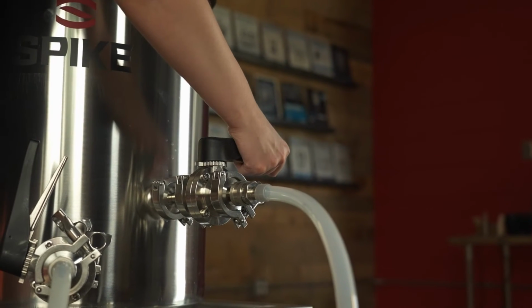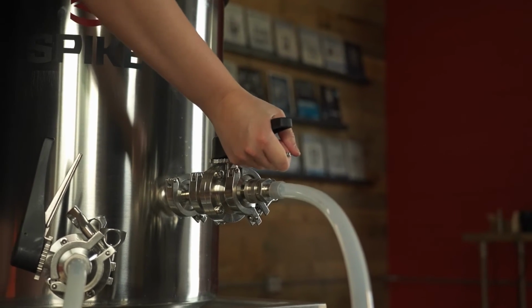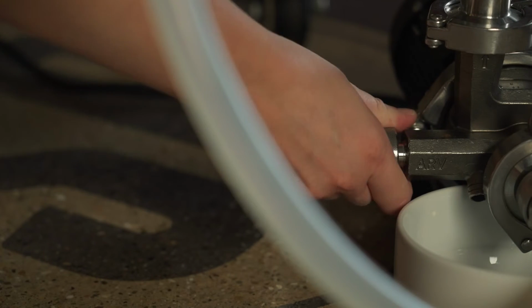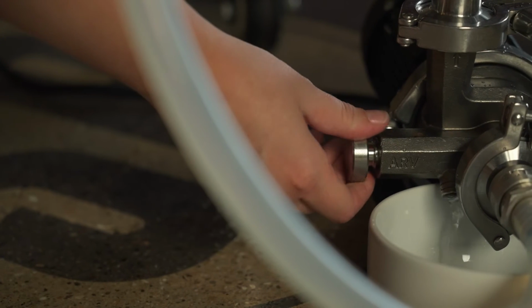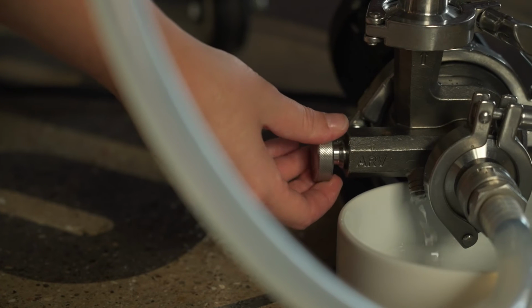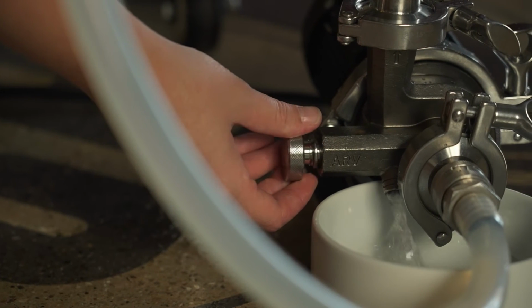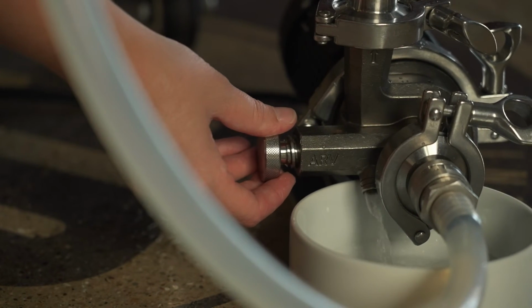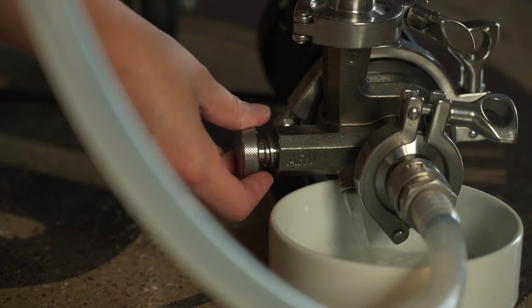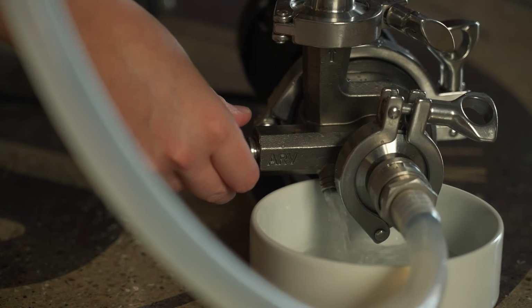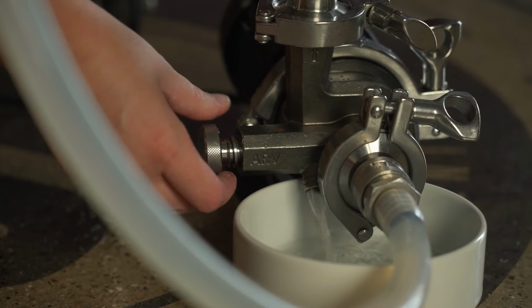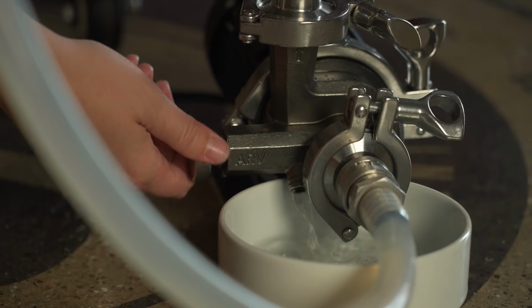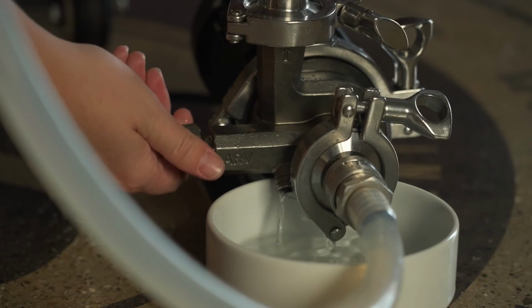You'll now want to prime your pump, removing any air in the lines. First, unscrew the air release valve, ARV, a couple turns until you see a solid liquid stream start to come out of the barbed bleed port. You can use a small cup or 3/8-inch tubing to catch the liquid coming out. Next, tighten the ARV until it's fully closed. Your pump is now fully primed and clear of air.